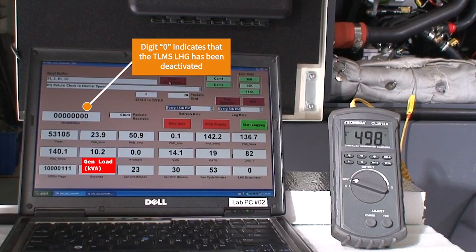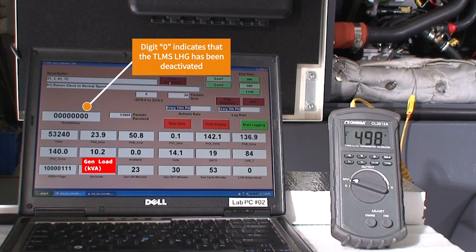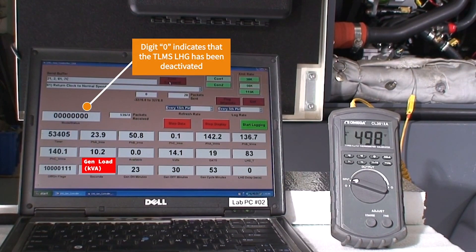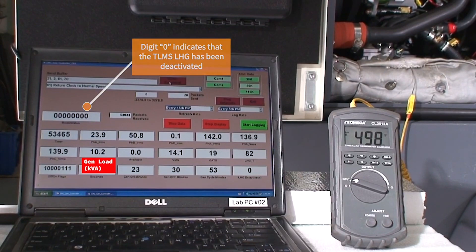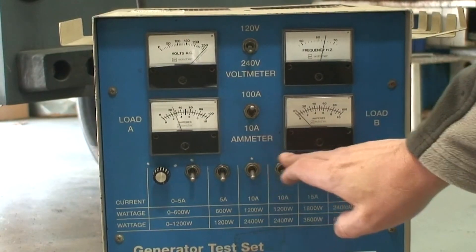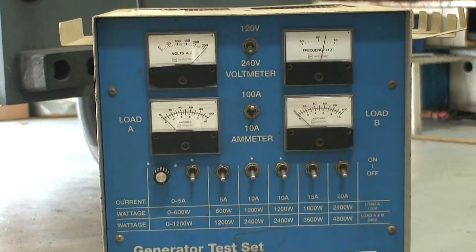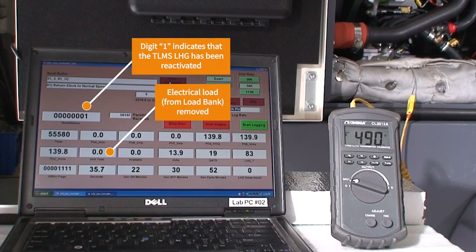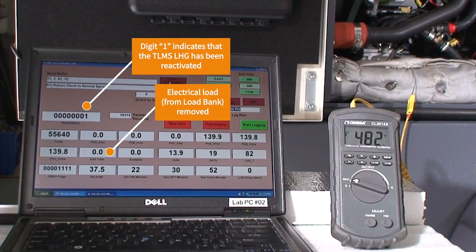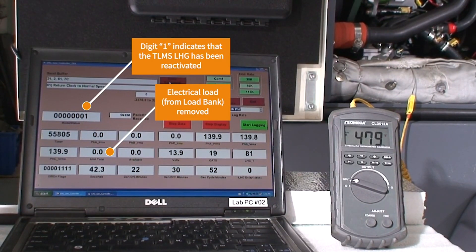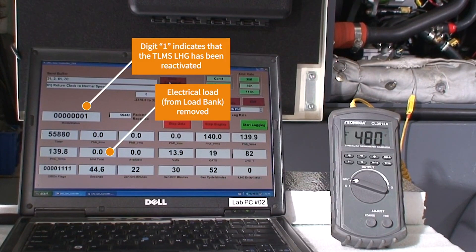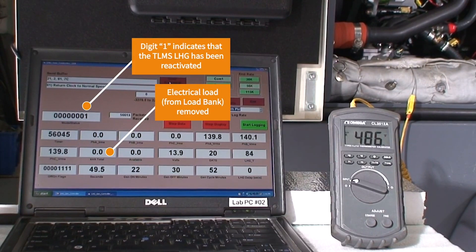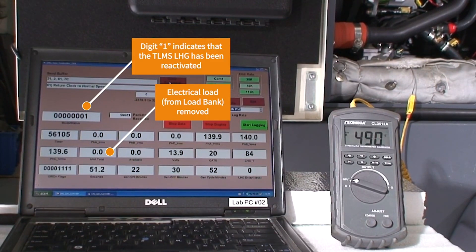We will now turn off the load bank, reducing the electrical load to zero, and the thermal load management system will immediately react by reactivating the LHG. While the load bank was applying 10 kilowatts, the exhaust gas temperature was sitting at about 490 degrees Fahrenheit. Note that now we have removed the load bank current and the LHG has been re-engaged, the exhaust gas temperature is sustained at about 490 degrees Fahrenheit.